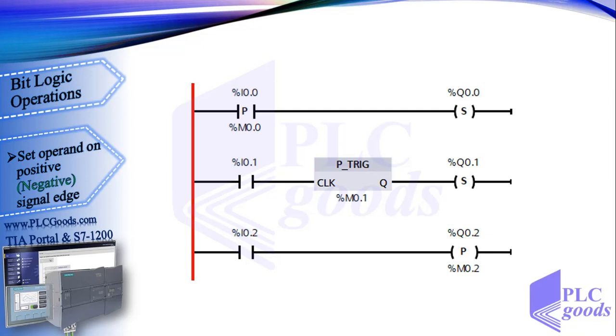Now for a short review of the instructions covered in this video. In each line of this program, an instruction sensitive to a positive edge signal is used. The first instruction is sensitive to a zero-to-one change in I0.0. When the value of that address changes from 0 to 1, this instruction generates a pulse at its output. A set instruction is typically used to latch the state, so Q0.0 remains on. If a simple assignment is used instead, Q0.0 will be on for only one program cycle — about 5 ms.